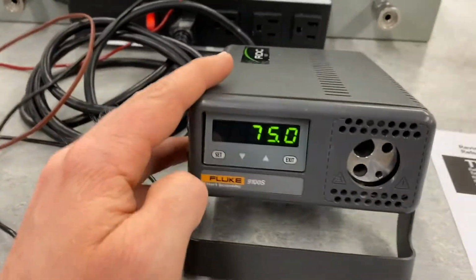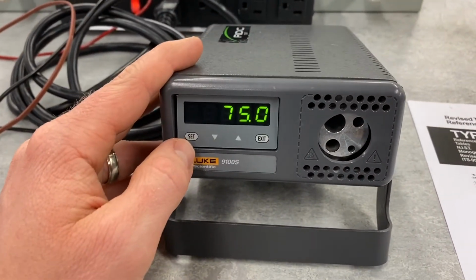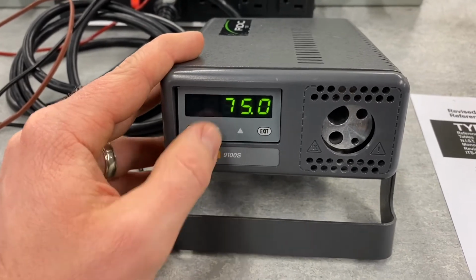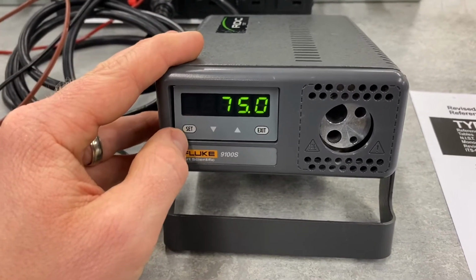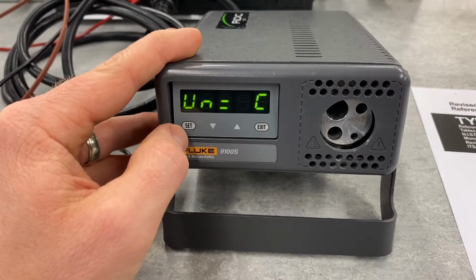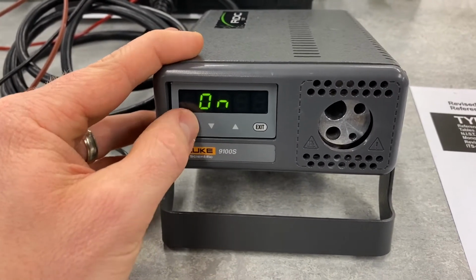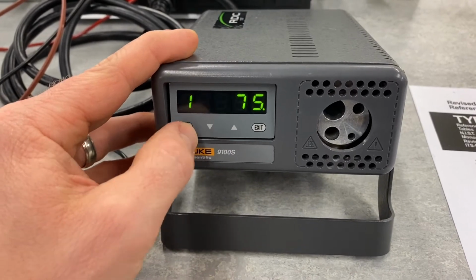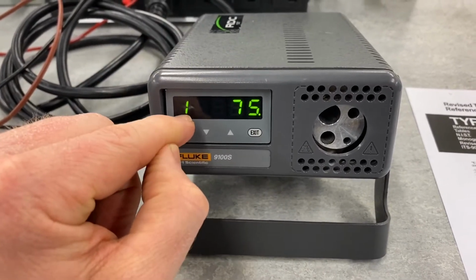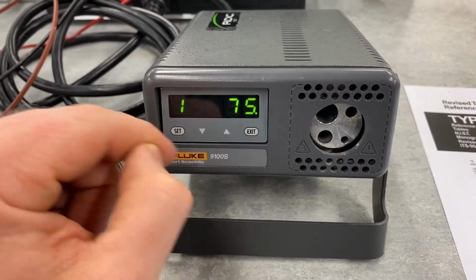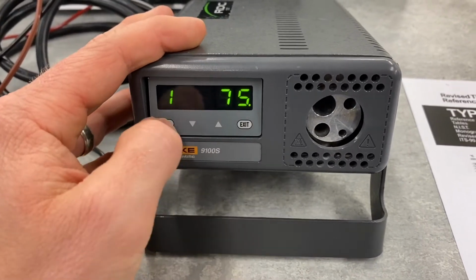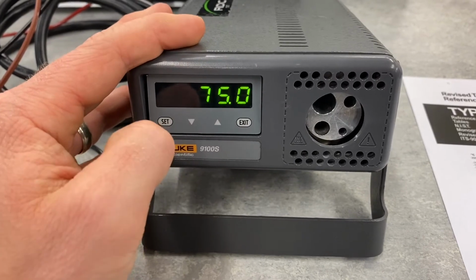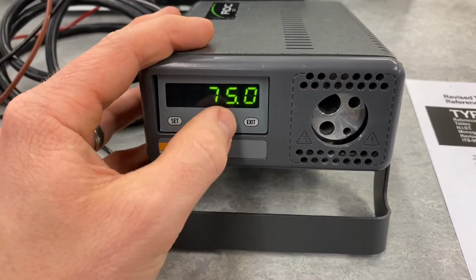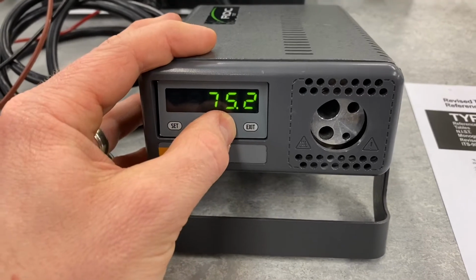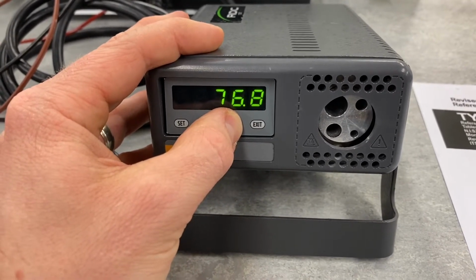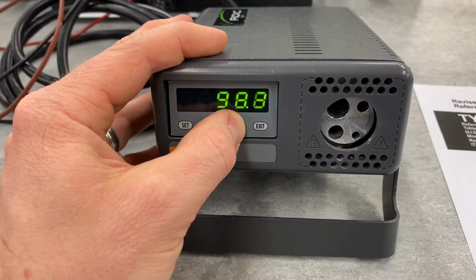Right, so in the next step of the lab here, we're going to be needing a temperature of 125 degrees C. So we're going to change this. Right now it's set for 75, you can see, but I'm going to change this by pressing set and toggle till we get a screen that has a value 1, 2, 3, or 4. This is a stored value of 75. We want to modify that, so we'll select the value we want to modify. So select that, we'll press set, and then we will change the value. So we want to go up to 125 degrees C, so I'll increase this value to that.